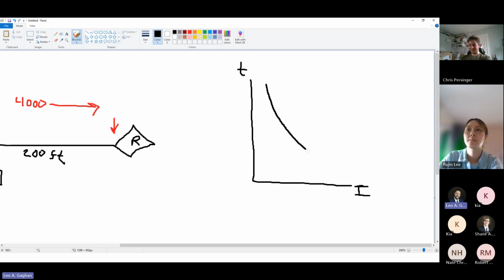So you can see inverse time has that characteristic there. It's got that curve. As current goes up, time goes down. That's just because the more current you have, the more energy you have, and the quicker you can damage equipment. You want your relay to operate faster. So that's what I mean by inverse time.